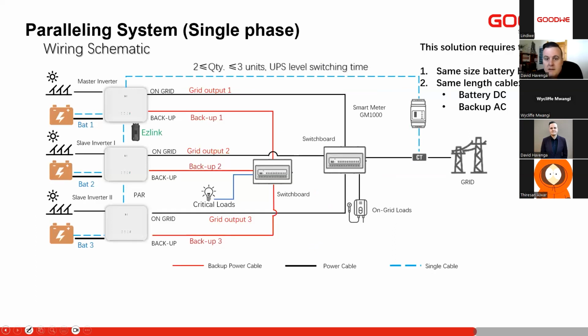So then we'll go over to paralleling. If we are paralleling the ES inverter, we'll make sure to complete everything else that we've already gone through on each inverter individually. So we make sure to commission them, make sure to do all the settings on them. Each inverter will have the same settings on. And then we will go into paralleling. Now that everything's commissioned, everything is set correctly, our battery's connected, our grid's connected, all of that, we make sure to have the backup loads off.